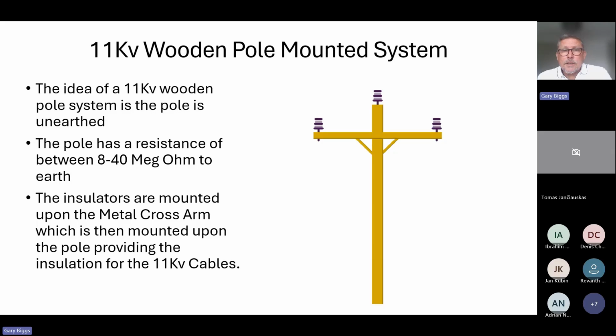But obviously, if you've got an insulator that's broken down, you want to know that, and you will have an indication in the substation that there is a leakage going on. But it will allow the system to still carry on working whilst you find that faulty insulator. Now, insulators, generally speaking, either go completely or they start to leak to earth. And when they start to leak to earth gradually, they will get worse over time. That may be because the insulator has cracked, has got impurities in it which have broken down over time, or it could be physical damage due to weather, maybe, or animal attacks or whatever. But if the insulator hasn't fully broken down, the system will hold up and, as I said, deliver electricity.